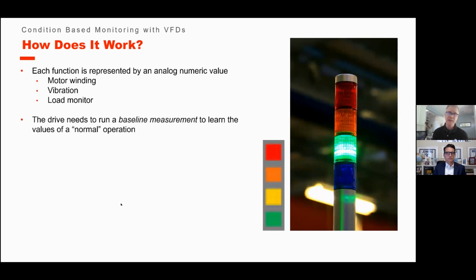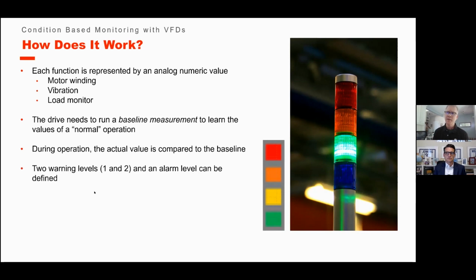The drive needs to run a baseline, like we said. So once the machine is broken in, if it's brand new or if it's been running a while, we want to develop a baseline of the data and the values as the machine is running in a great state. So we develop that baseline to learn the values of normal operation. Then during operation, the actual value is compared to the baseline. So once we get into operation, we're comparing those values to the baseline that we just recorded. Then there are two warning levels, warning 1 and warning 2. And you have to define those through the thresholds.